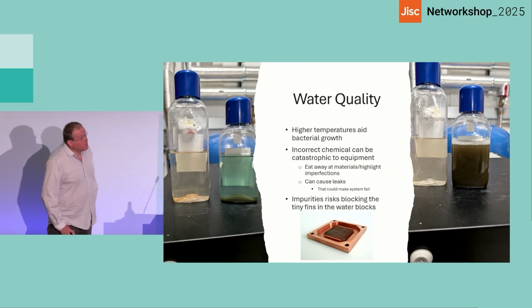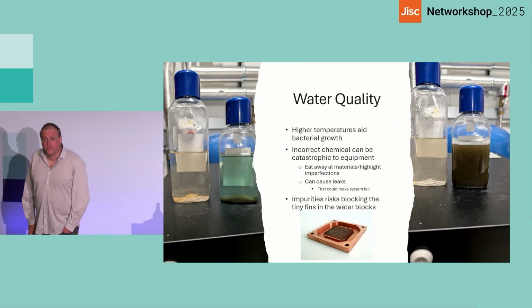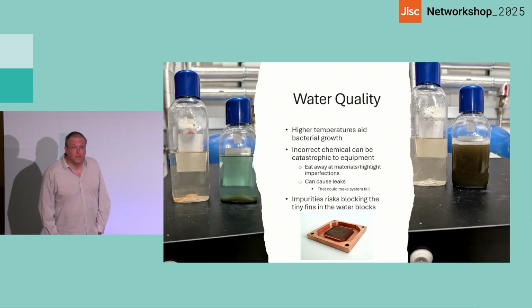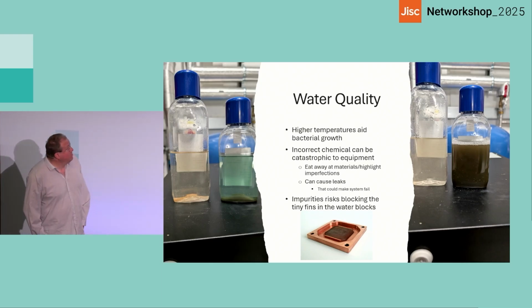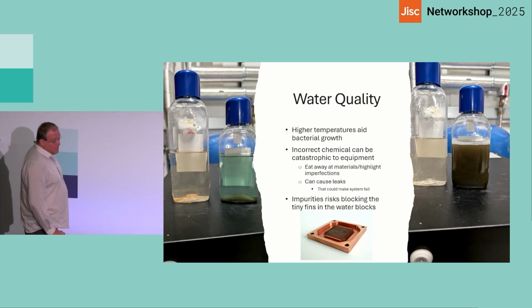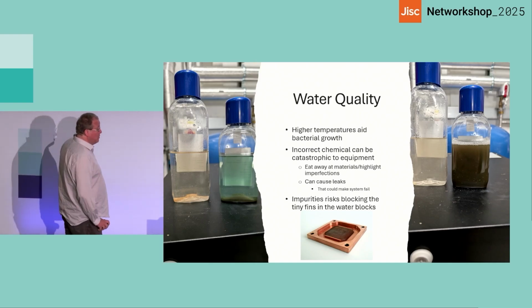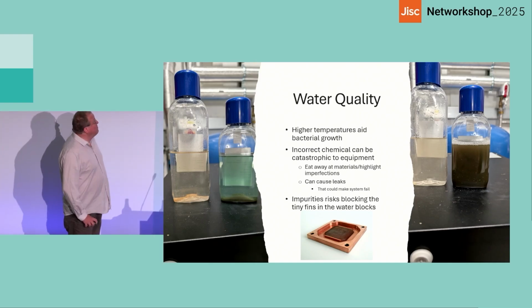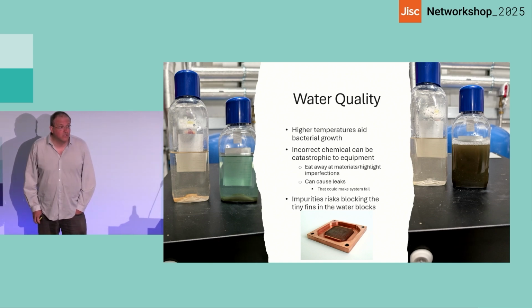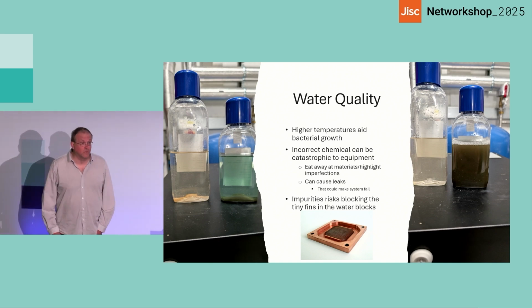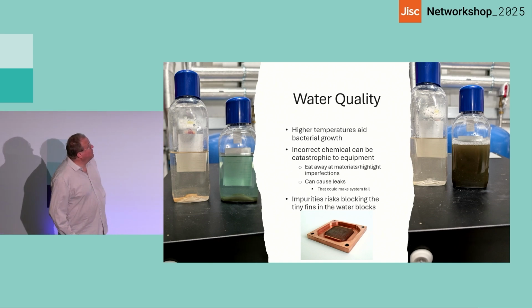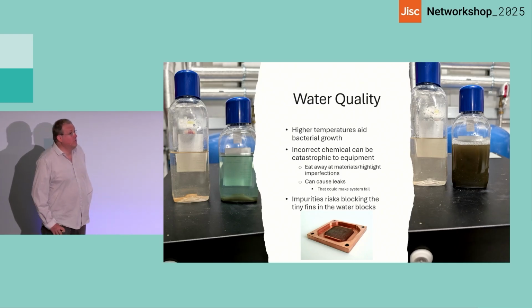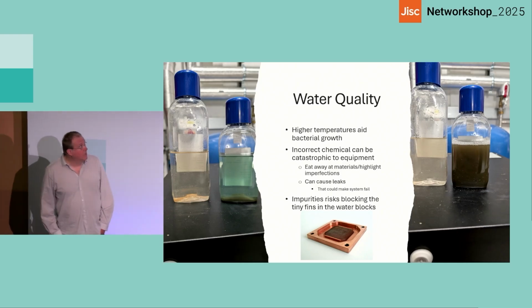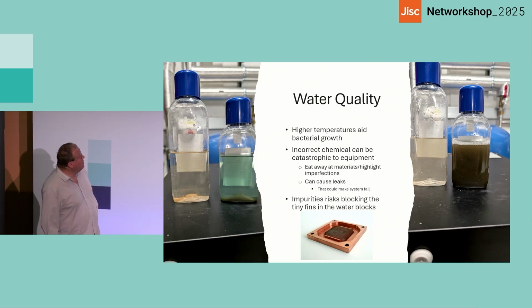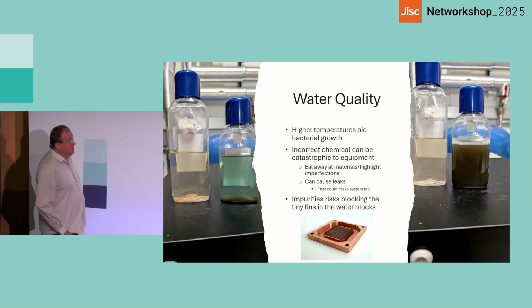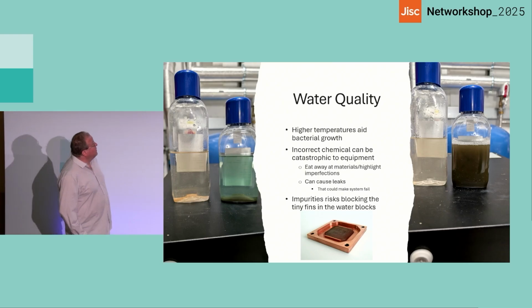And that will restrict your water flow through it. That will restrict how much cooling it can do. That'll also possibly make the thing crash randomly for you. So purely, these systems need a lot of water flowing through them. If you don't get the water flowing through, they don't cool. So if they get bunged up, parts of them may overheat when you're doing certain operations, and they'll just randomly crash on you. So you need a very good water solution, and you need to make sure it's sampled and checked appropriately at regular intervals. And any potential issues, you actually go and check it out and get it cleaned, flushed, and rectify the problem.